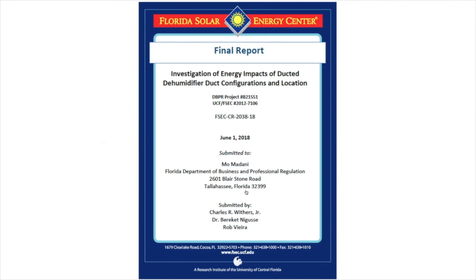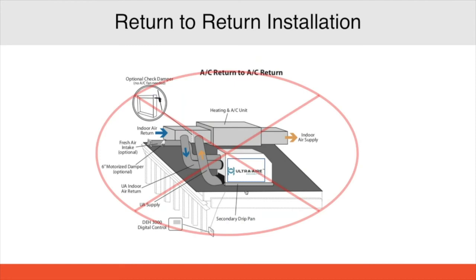So much so that Florida Solar Energy about two years ago came out with a study on different dehumidifier installs. And basically, their conclusion was that a return to return is the most ineffective and energy intensive install, and they do not recommend it. And that's because when we'll go back here, when we're dehumidifying that air and putting it back into the return of the AC system, we're heating up the coils of the AC, which means it's removing less water. And then when that AC shuts off and the dehumidifier potentially is on, if that's how it's been set up, it's going to re-evaporate that air back into the living space. But again, you really reduce the latent capabilities of your AC system when you do this sort of install.